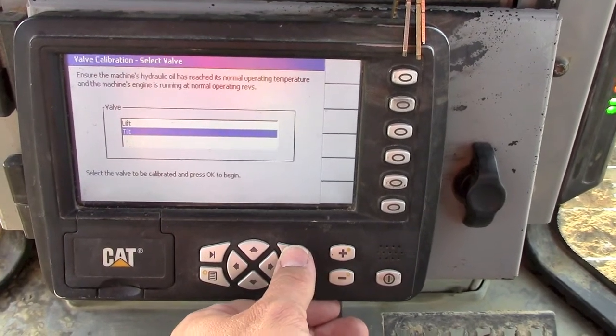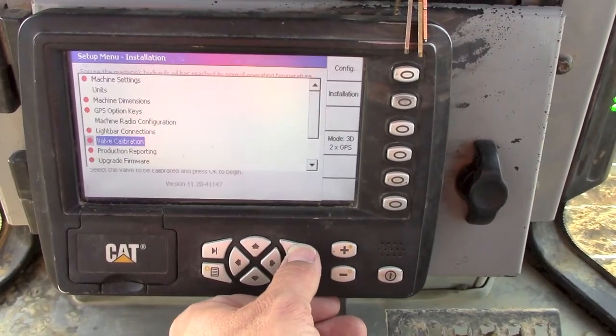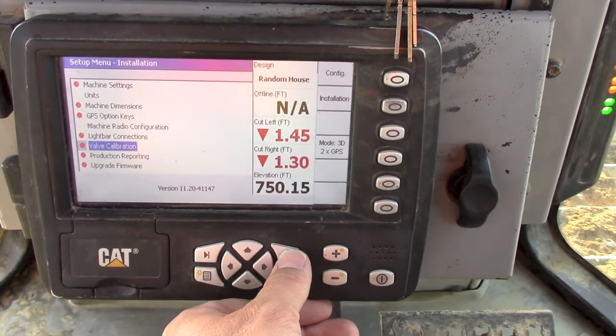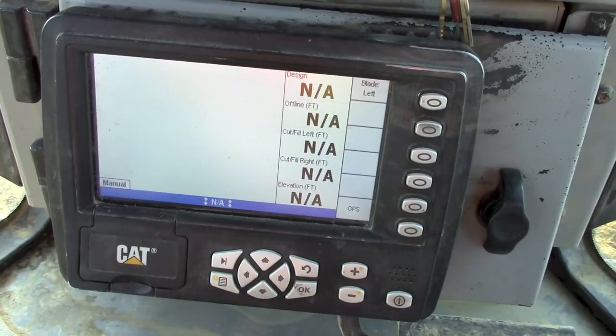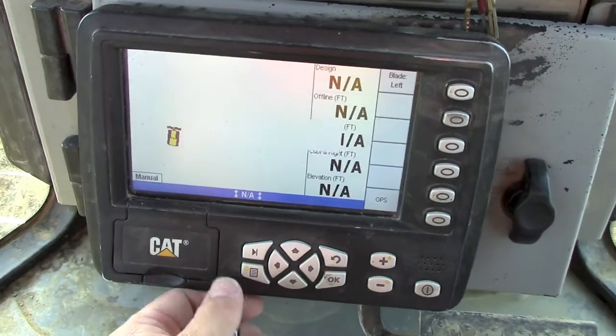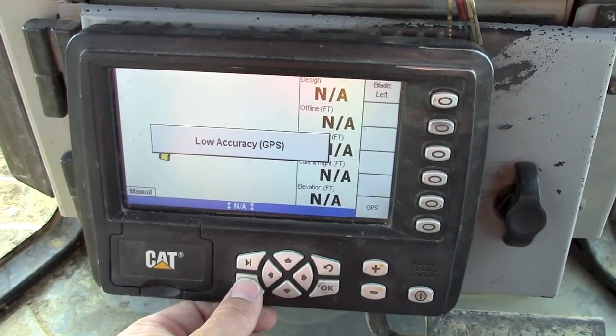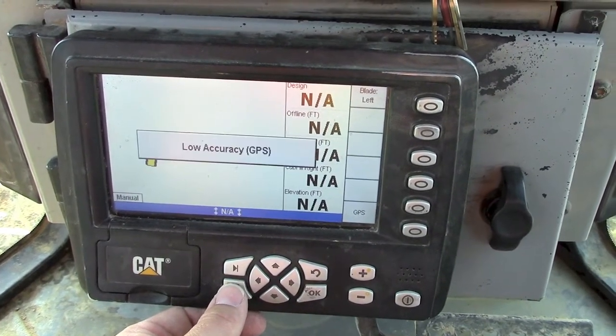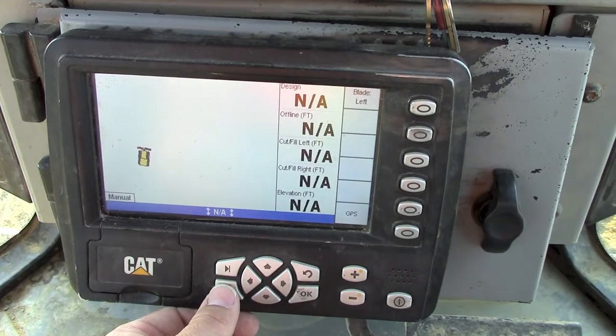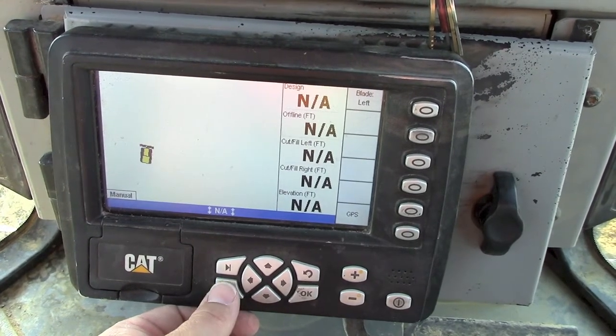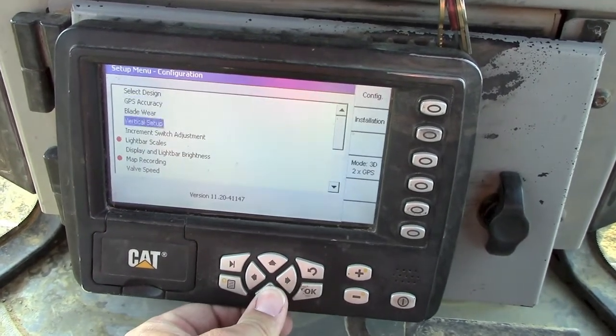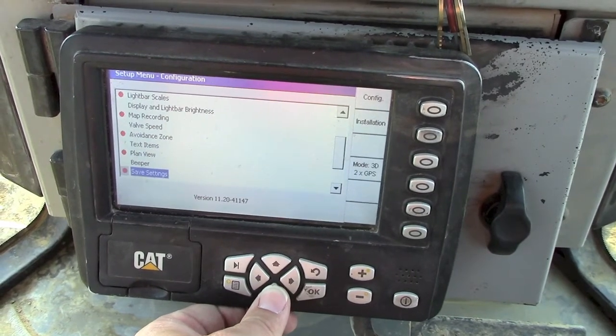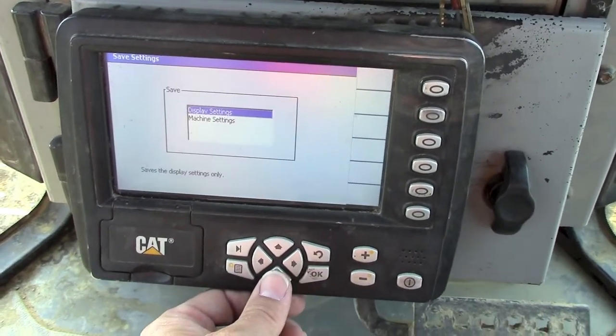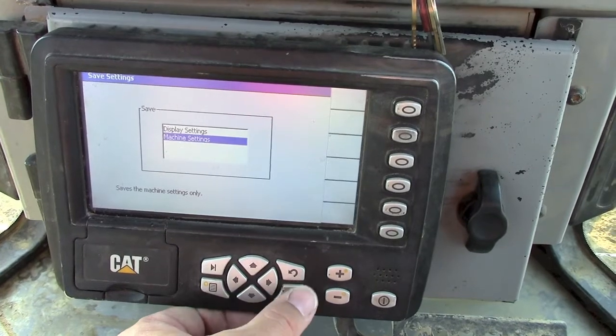We can escape out of this screen using the back button to get back to our normal operating screen. At this point, it is a good idea to save the machine file with something that has the date so that you know it is the latest saved file with that particular valve calibration included. To do this, we press the menu button, scroll down to Save Settings. We need to save the machine settings.